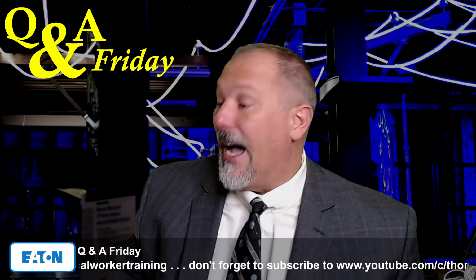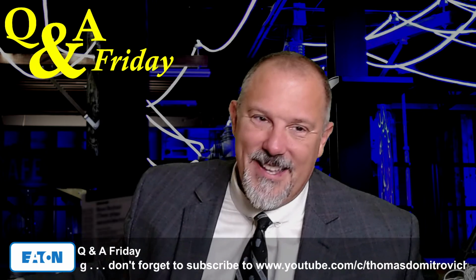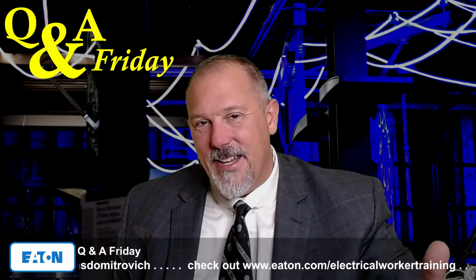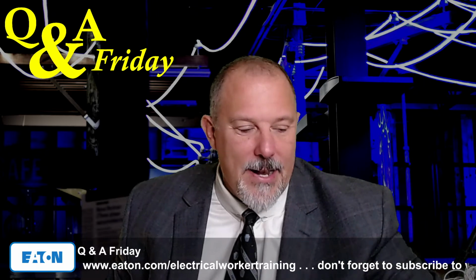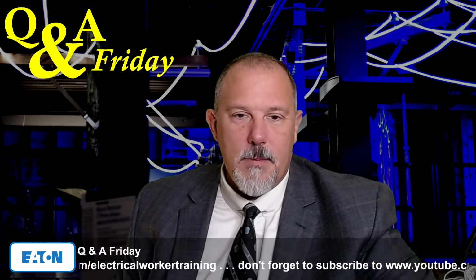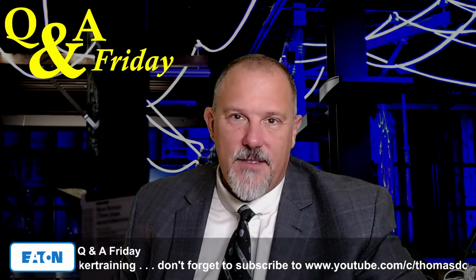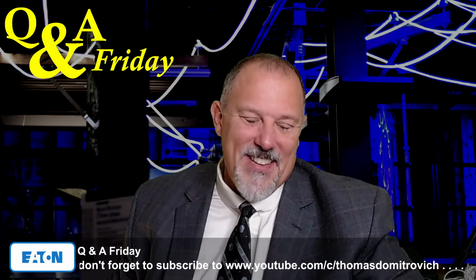but I'll never forget, I had somebody give me an available fault current. I asked the class what the available fault current was, and they do the math, and one of the engineers raised his hand and says, "I got it." And I said, "What is it?" He goes, "43,362 amps, 0.57764." And I'm like, you had me at the first two digits. The accuracy, how many decimal points you take things out to, matters in some cases and doesn't in others.